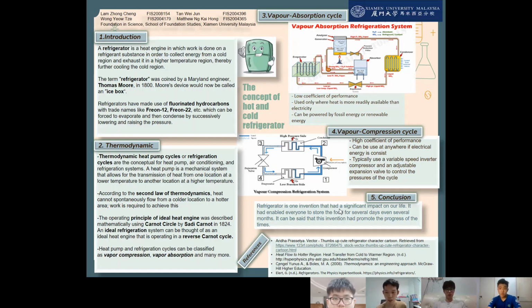Then a liquid pump moves the strong solution from the absorber to the generator, where on heat addition, the temperature and pressure increase. Then the refrigerant vapor is released from the strong solution, which turns into the dilute solution and is moved back to the absorber by the liquid pump.